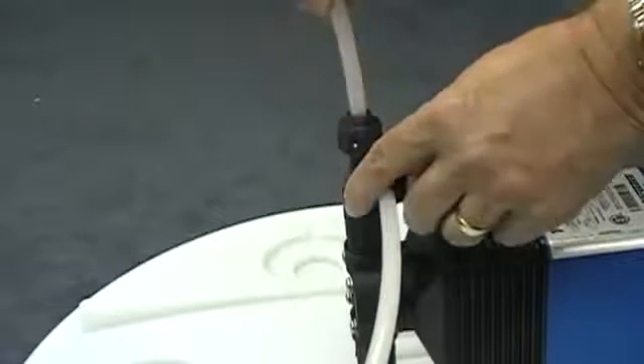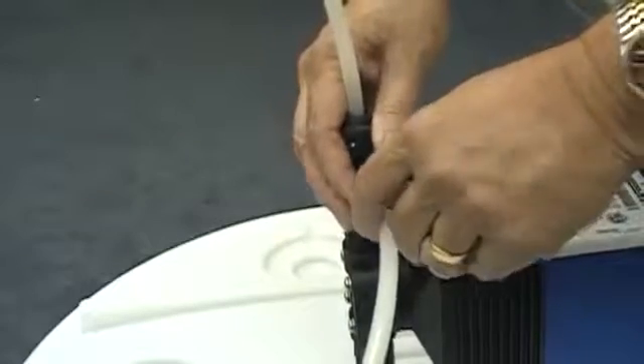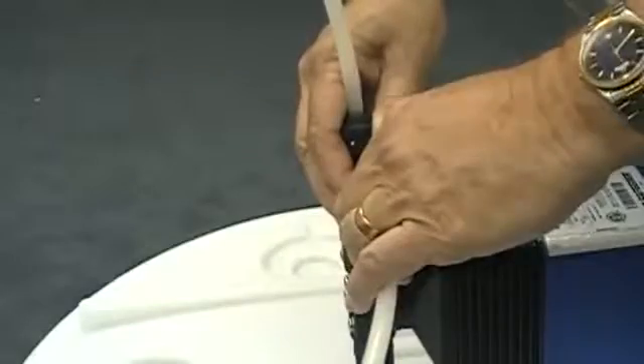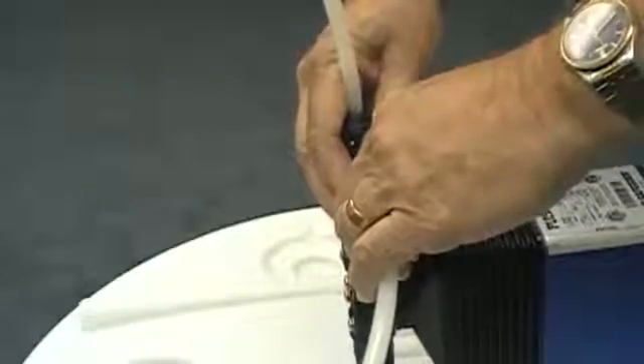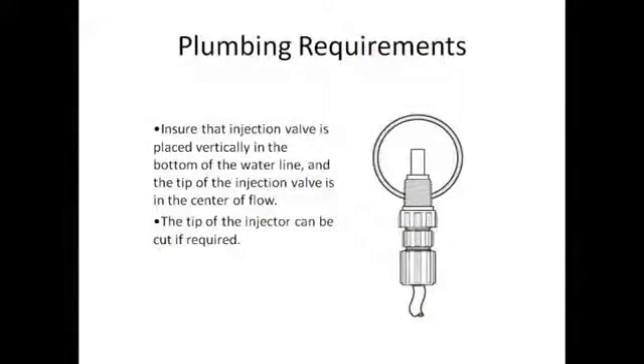To make connecting the tube easier, they may be warmed prior to placing them on the compression fittings. Ensure that the injection valve is placed vertically in the bottom of the water line and the tip of the injection valve is in the center of flow. The tip of the injector can be cut if required.